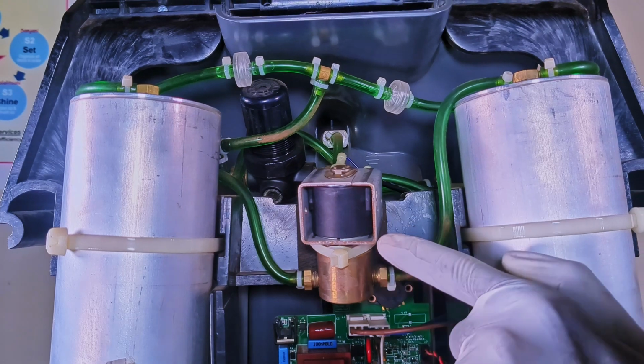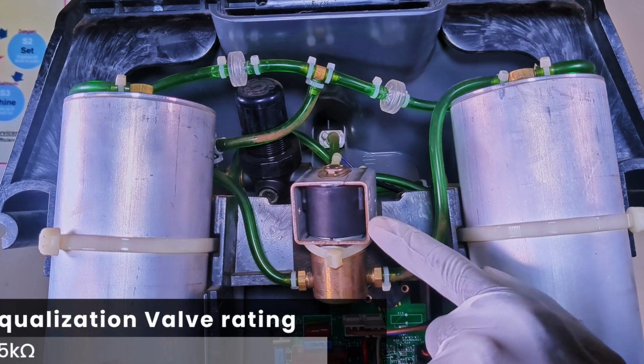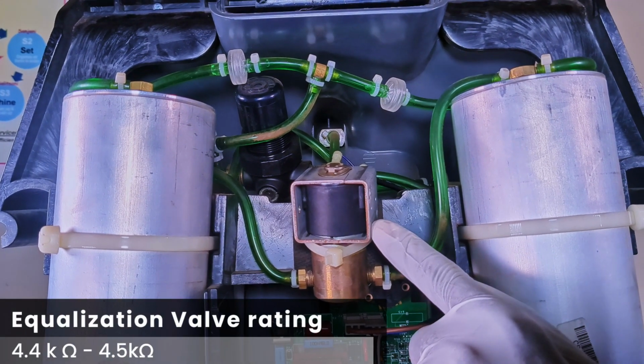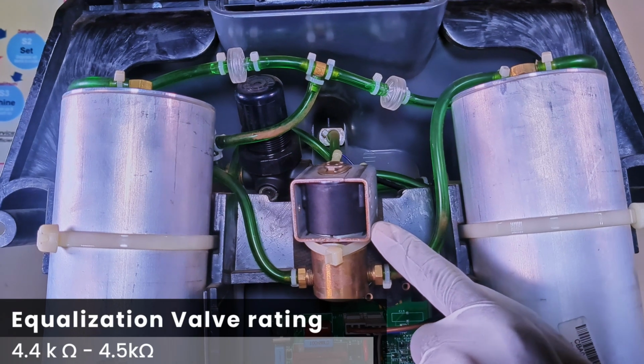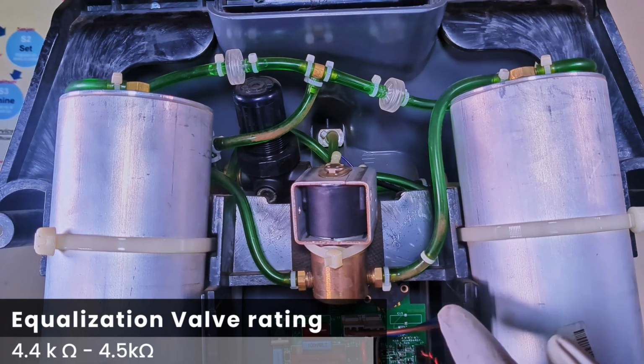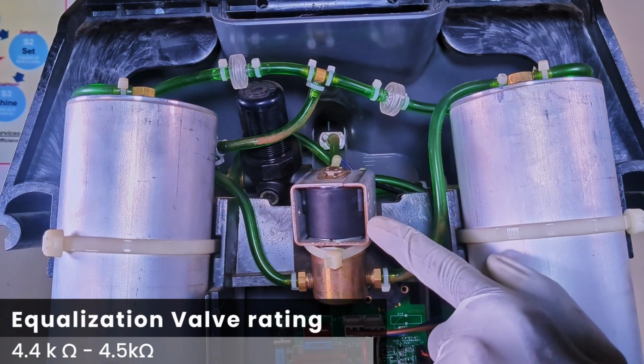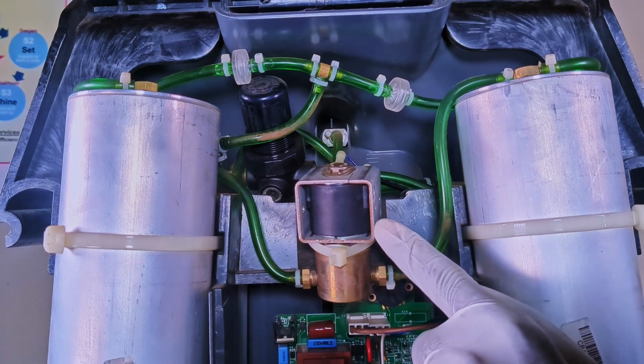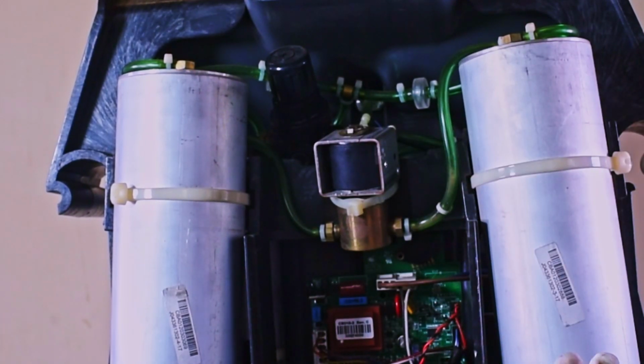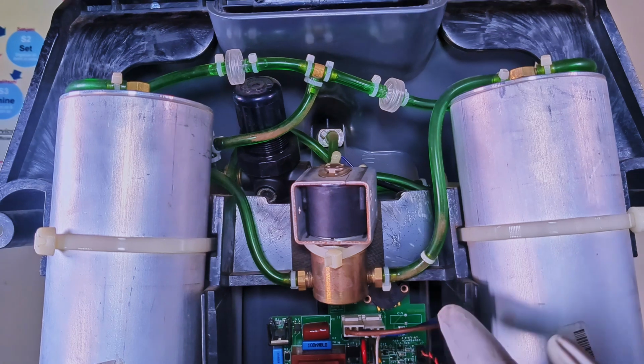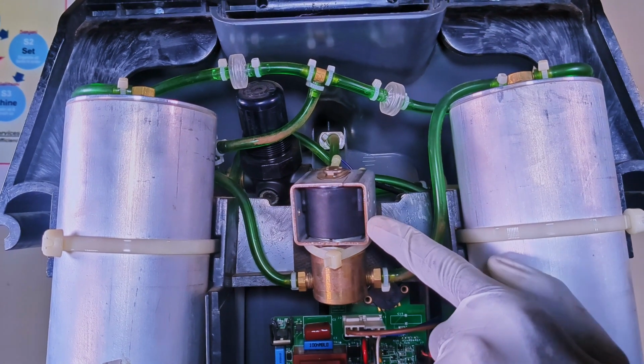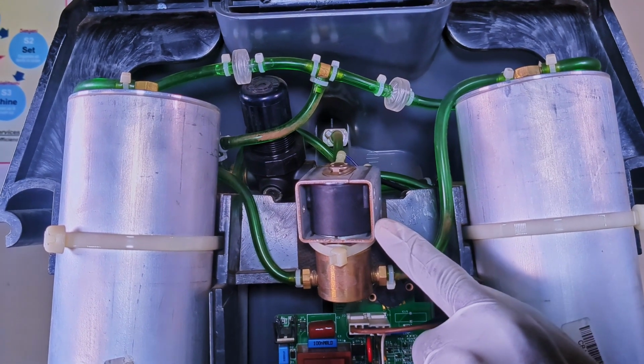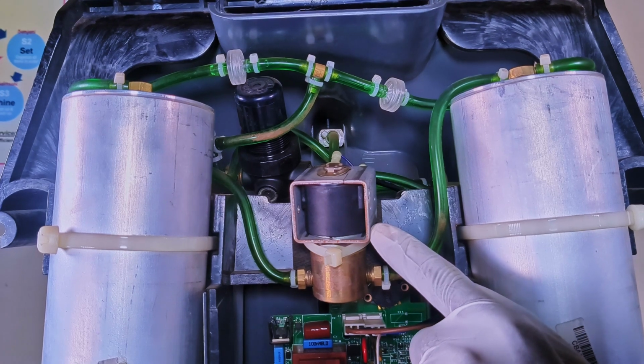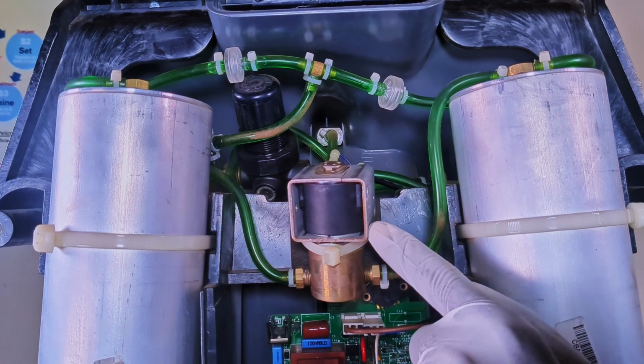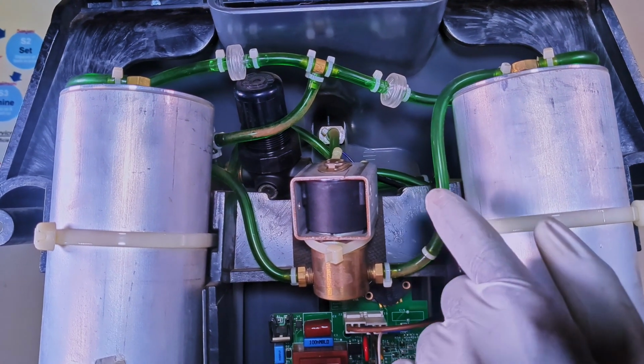So over here, we have another solenoid valve. So this is actually the equalization valve. This valve facilitates the pressurization of the sieve bed as well as nitrogen purging during the depressurizing cycle. So this valve also allows part of the oxygen produced in the active bed to enter the other sieve bed, thereby reducing energy requirements and increasing efficiency.